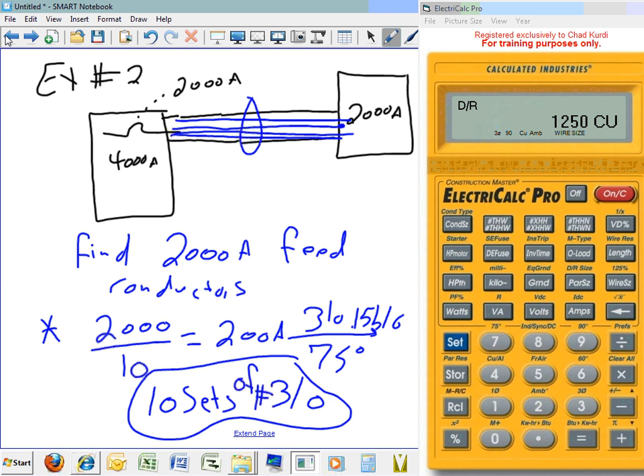So what are you saying? If we are creating this panel to panel, we need. If it's not incorporated, most of the time, I want you to get into the habit of this: when you make up your mind about the panel based on the overcurrent device, you size the conductor to match the overcurrent device. That's always what we do. Now the question is, your question should be to me, how the heck did you come up with this 2000 amp? I tell you how. I took all my continuous load here, multiplied it by 1.25, plus all my non-continuous load here, added them up. I came up with 1,950. What's my next overcurrent device? 2,000. I didn't walk you through this calculation, but it's coming when we do the load calculation.